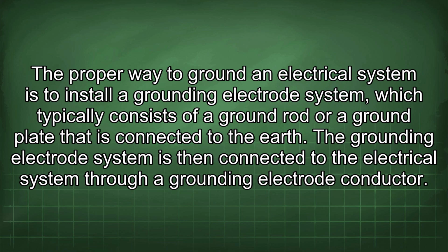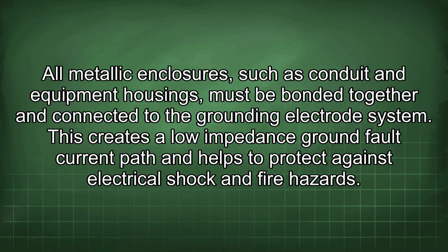The proper way to ground an electrical system is to install a grounding electrode system, which typically consists of a ground rod or a ground plate that is connected to the earth. The grounding electrode system is then connected to the electrical system through a grounding electrode conductor. All metallic enclosures, such as conduit and equipment housings, must be bonded together and connected to the grounding electrode system. This creates a low impedance ground fault current path and helps to protect against electrical shock and fire hazards.